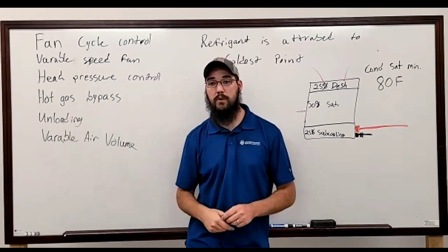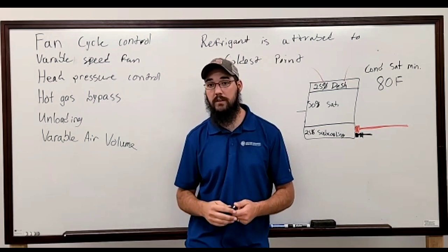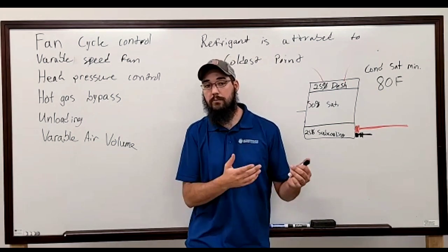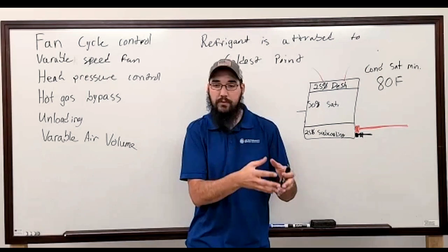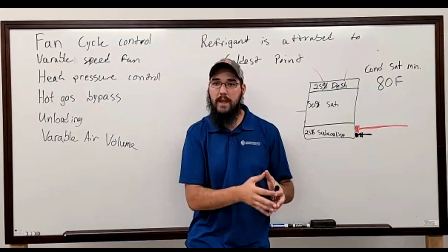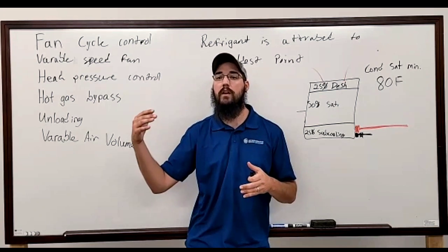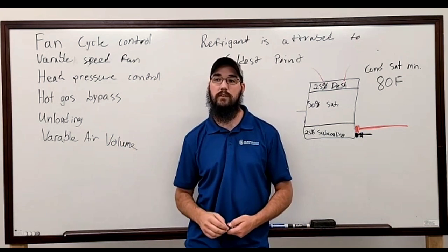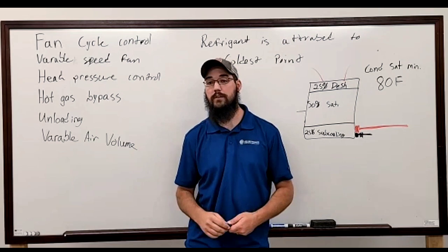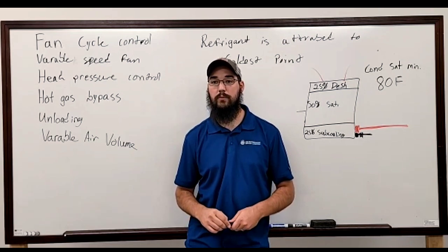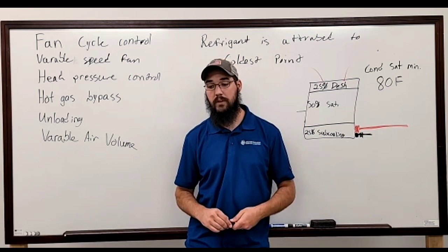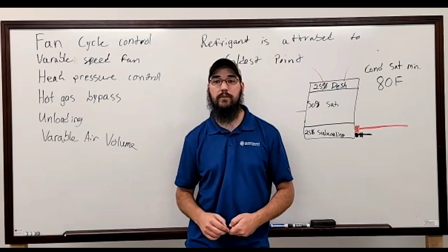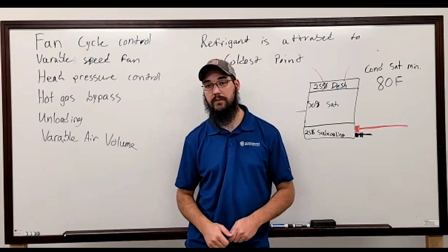We run all kinds of motors. Most of the systems that are variable speed are specifically designed to be variable speed. Daikin is a prime example, where they're not limiting. They have specifically tailored compressors that are made to run at higher frequencies to achieve the efficiencies and the speeds that they're looking for. That's just the way it is. Even a 60 hertz motor, you can ramp above 60 hertz, given the right parameters. But you have to do it properly.